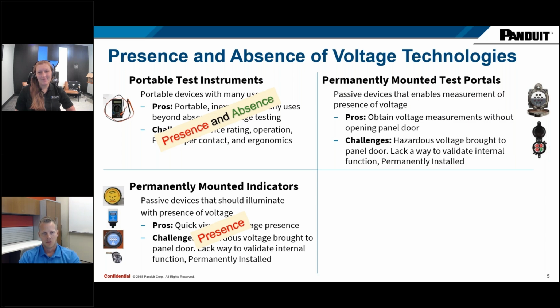But so another product that you'll see out there a lot of times, and sometimes these will have lights as well, but they're test portals. So they're a point where you can measure and put your meter on them. Passive device, again, you can measure presence of voltage because you can only really tell if it's there. It's great because you can get those measurements with the door closed, right? You're not having to open that cabinet door and do those measurements, right? You can do that from the outside. So that is a pro for sure.